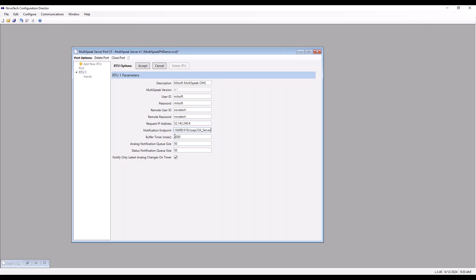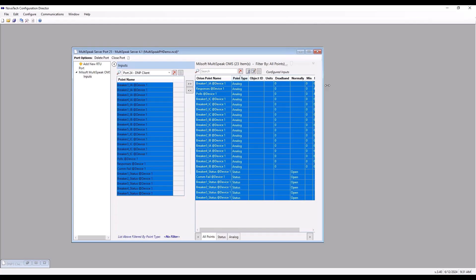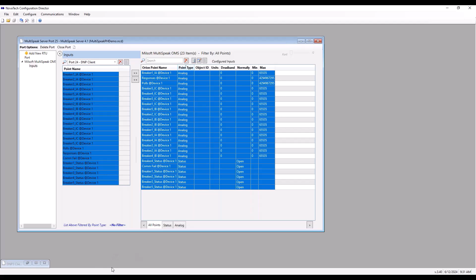We'll hit accept and update the RTU. On the inputs list, we'll filter by the DNP client we made, select all our breaker statuses and breaker currents, and map them over. We'll hit save, and at that point the configuration file is ready to be uploaded with the multi-speak module configured.